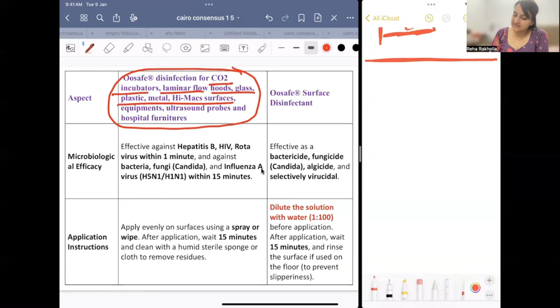See, the Oosafe disinfectant for CO2 incubator, laminar flow hood, glass, plastic, high touch surfaces, equipment, ultrasound is used without dilution. We do not need dilution for this, but the surface disinfectant needs dilution with water, 1:100. It is effective against hepatitis B, HIV, rotavirus within 1 minute, and against bacteria, fungi, candida, and influenza A virus within 15 minutes.